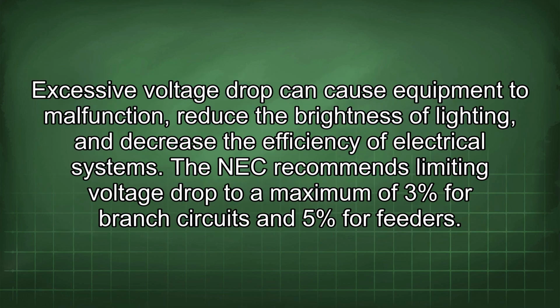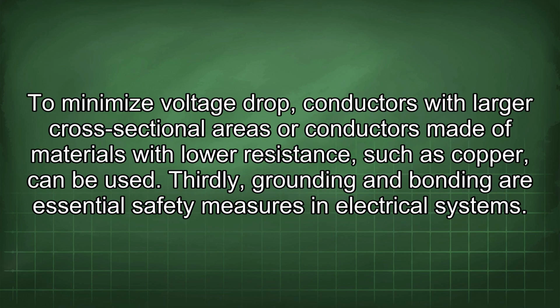Excessive voltage drop can cause equipment to malfunction, reduce the brightness of lighting, and decrease the efficiency of electrical systems. The NEC recommends limiting voltage drop to a maximum of 3% for branch circuits and 5% for feeders. To minimize voltage drop, conductors with larger cross-sectional areas or conductors made of materials with lower resistance such as copper can be used. Thirdly, grounding and bonding are essential safety measures in electrical systems.